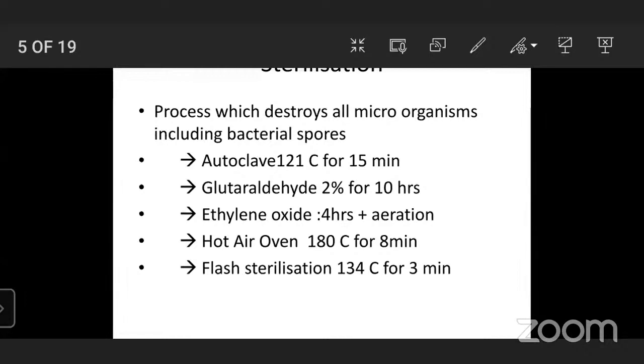For 2 to 6 hours, if you achieve that contact time, it will be disinfection, and for more than 6 hours you will achieve sterilization. But generally, we don't use an extended contact time for glutaraldehyde of more than 6 hours, because it can damage the equipment or the surface. So what we commonly use for chemical disinfection of equipment is a contact time of say 2 hours, and that will lead to high level disinfection, not sterilization. That should be enough.